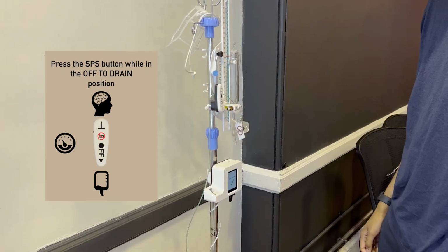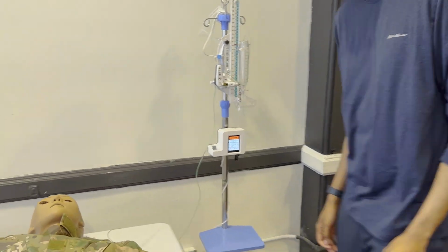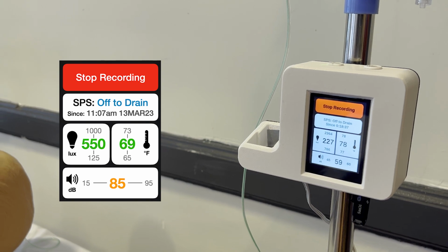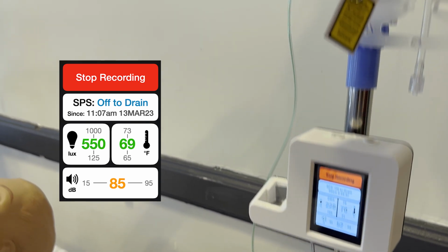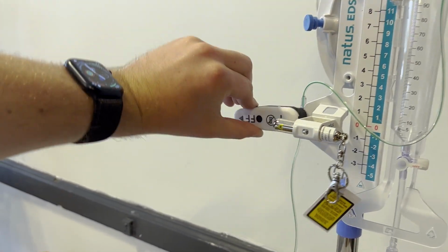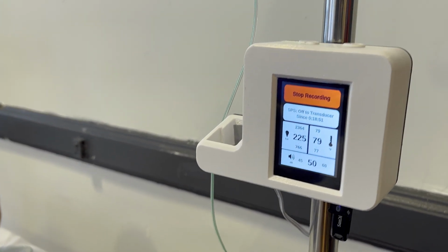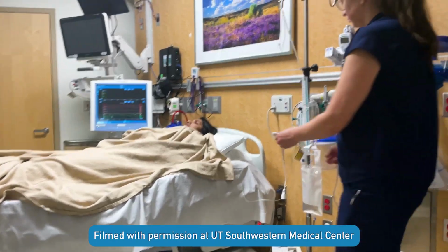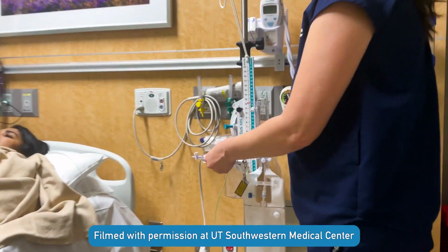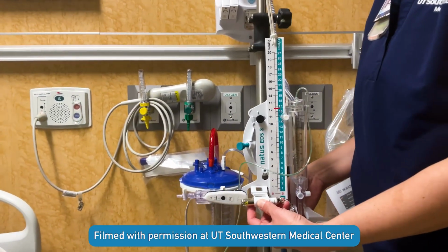At this point, calibration is complete and you are directed to the recording screen where you see values for light, sound, and temperature, as well as the stopcock position. You'll note when we turn the stopcock here, that value will be updated both on the screen and logged to our data file, ready for machine learning. It's natural for the nurses. This doesn't change any of the requirements for the nurses. It's just more accurate data with no additional work.